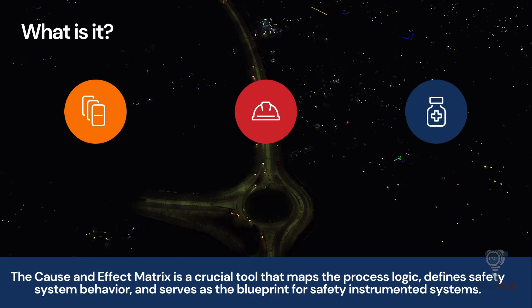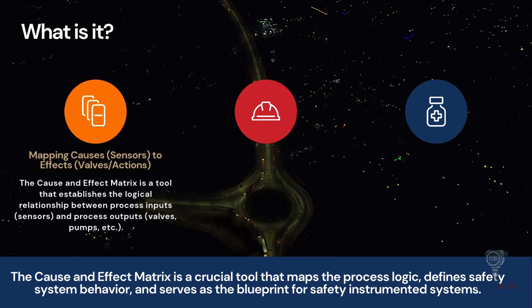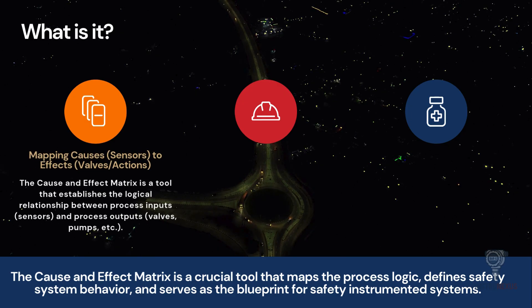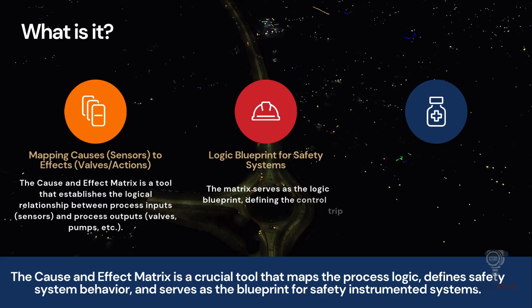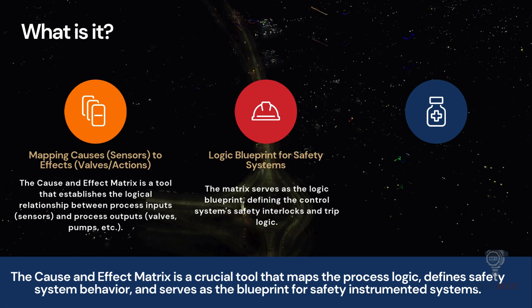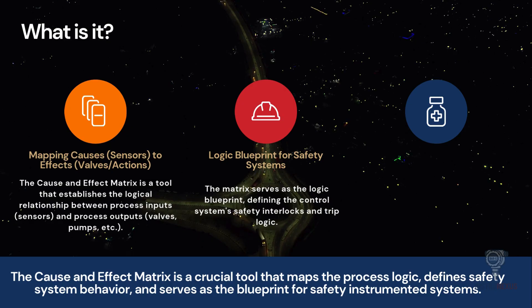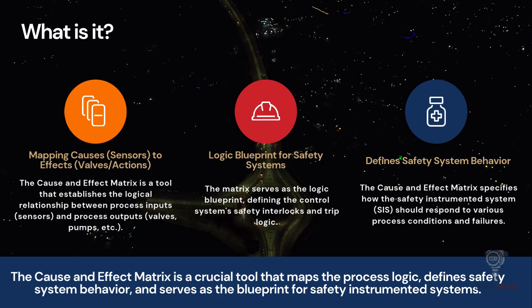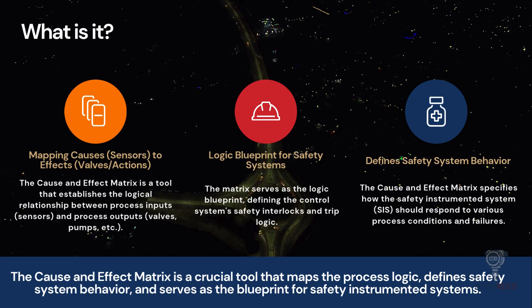So, what exactly is a cause and effect matrix? In the simplest terms, it is a tool used to map the relationship between process sensors, which we call causes, and the actions taken by valves or pumps, which we call effects. Think of it as the logic blueprint for your safety critical applications. In a complex processing plant, you have hundreds of inputs and outputs. This matrix organises them into a grid that defines exactly how the Safety Instrumented System, or SIS, serves to control the plant. It establishes the logical relationship between a specific process input and its required output, ensuring that everyone, from designers to operators, has a clear, comprehensive understanding of the system's behaviour.